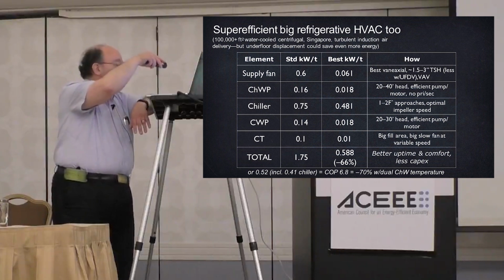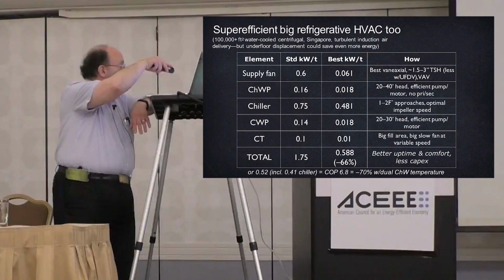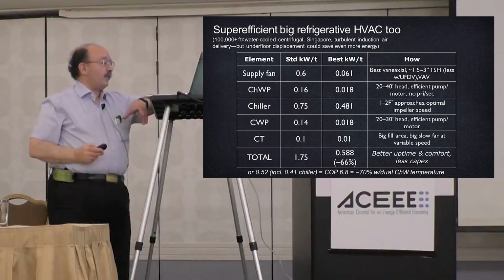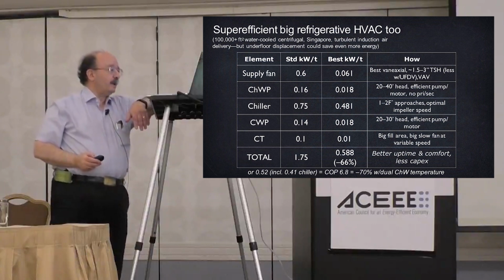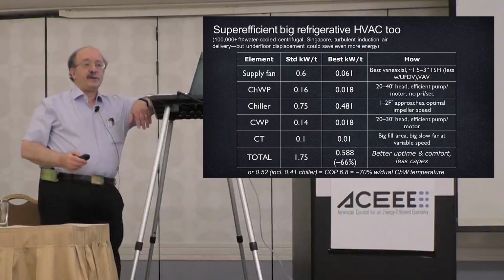And the whole system, supply fans through cooling towers, adds up to 0.52 kilowatt per ton if you go to a dual chilled water temperature, with separate coils for condensing and sensible cooling, and that raises the savings to 70% from normal practice. But again, it works better and costs less.